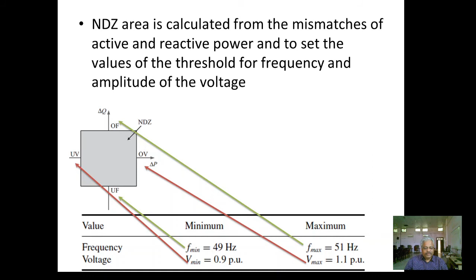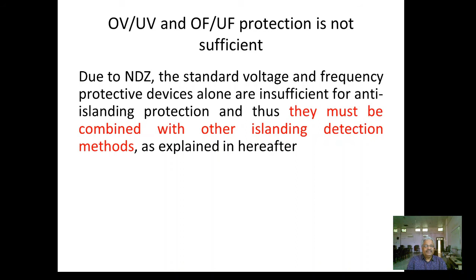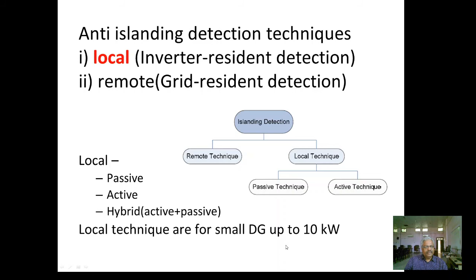The standard voltage and frequency protective devices alone are insufficient for anti-islanding protection, and thus they must be combined with other islanding detection methods, as explained hereafter. What are those methods? There are two types: one is local techniques, second is remote techniques. In local techniques, you have active techniques, passive techniques, or hybrid techniques. In remote techniques also there are different techniques, and we will see what they are. The local techniques are for small distributed generation up to 10 kilowatt.